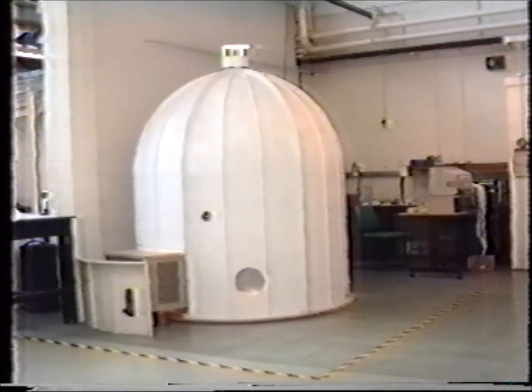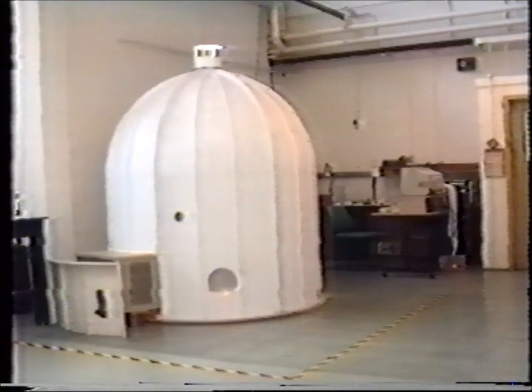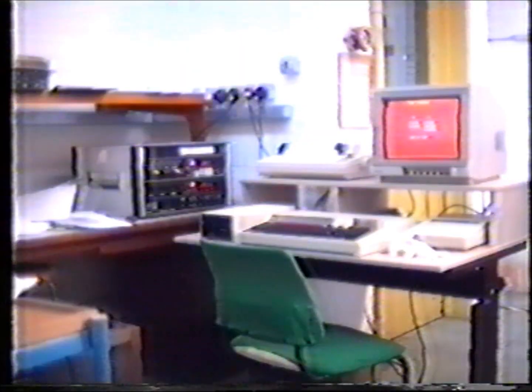Pyranometers, or solarimeters as they are often called, are calibrated in a glass fibre chamber in which 5 halogen lights are fitted around the circumference. These produce an even light level at about 500 watts per square metre and of a similar frequency range to that of natural solar radiation.